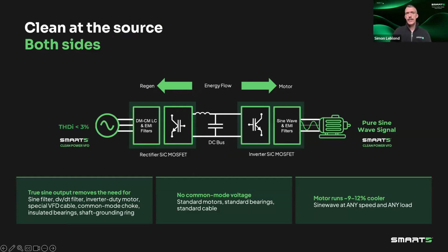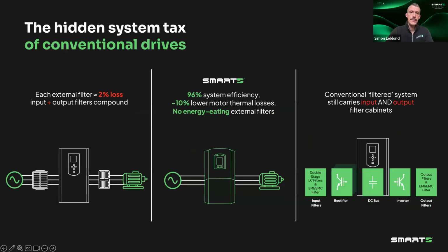So as I mentioned, not only do you get the low harmonics on the grid, you also get the pure sine wave to the motor that removes entirely any cable length limit, removes the common mode choke requirement or bearing fluting risk. And I know most of the data centers are new build, but you also get a great opportunity to retrofit non-inverter duty motors or standard cable applications. Also, because the motor is seeing a sine wave and not a PWM, it's running 9 to 12% cooler. And that sine wave is true at any speed and load profile, so it's not just full load as you'd have when specifying harmonics content.